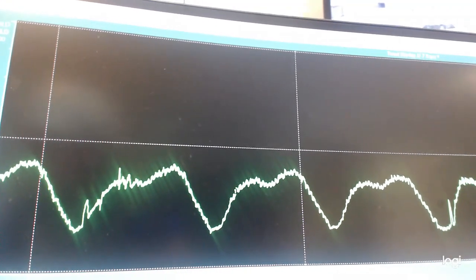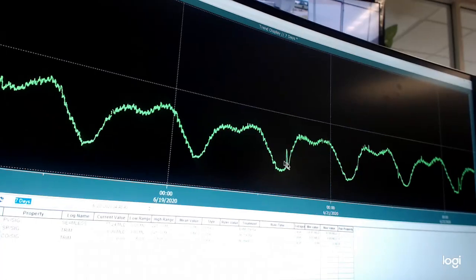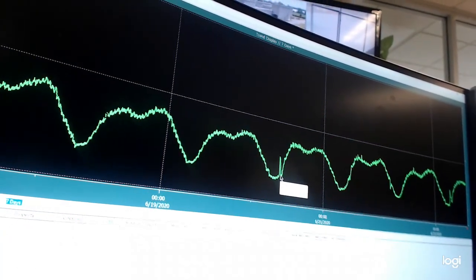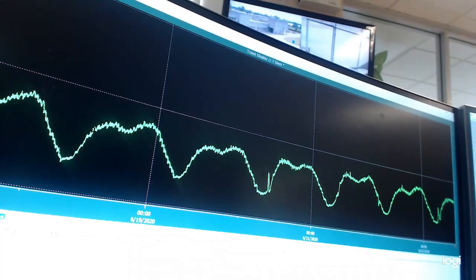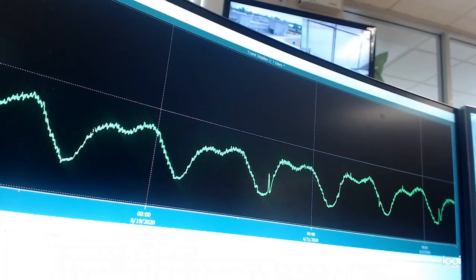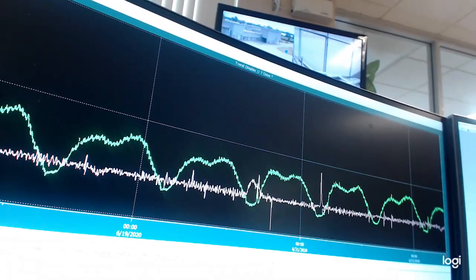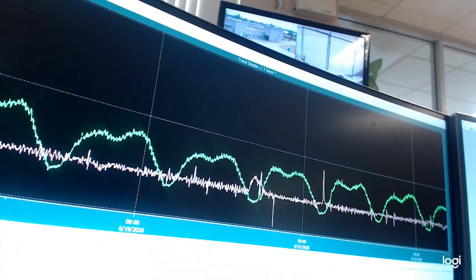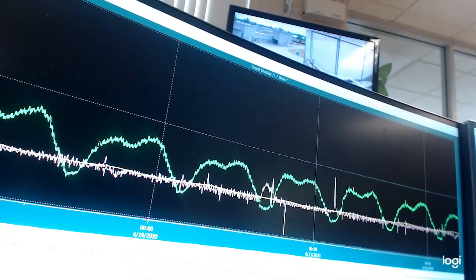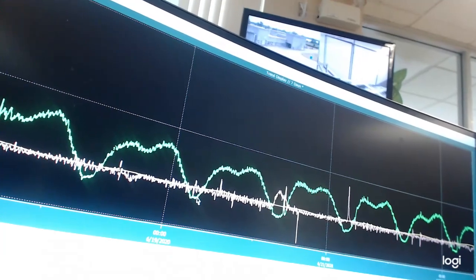Sometimes something goes wrong — here we have a peak because extra pumps were turned on or more fluid came in. On top of this we can add and drag information to compare our daily flow with the chlorine level in our disinfection system. You can see that at low flows there was a hump in chlorine. We can drag in the effluent temperature, which is fairly consistent, with a very mild pattern in the white line. We can add information to the graph, but the system is automated — operators are here to maintain and control it.